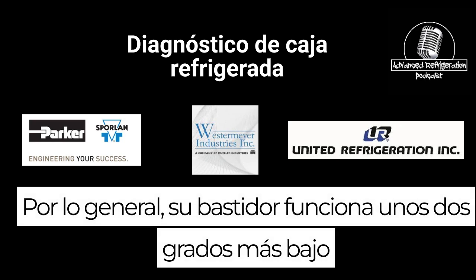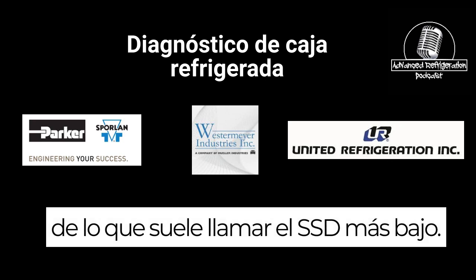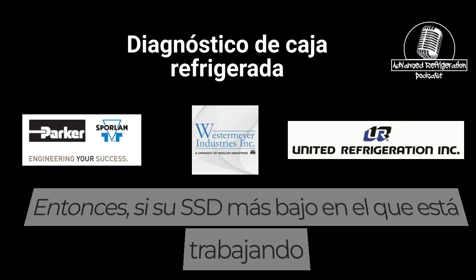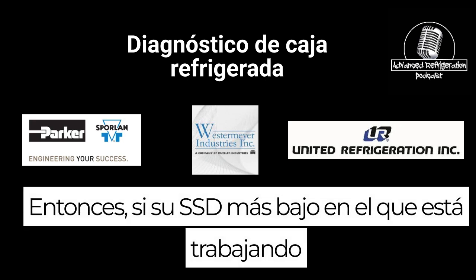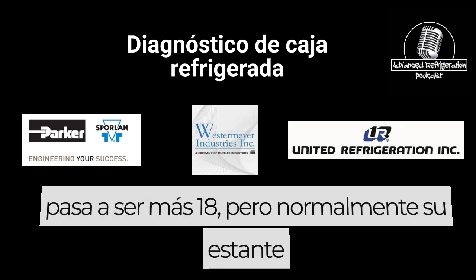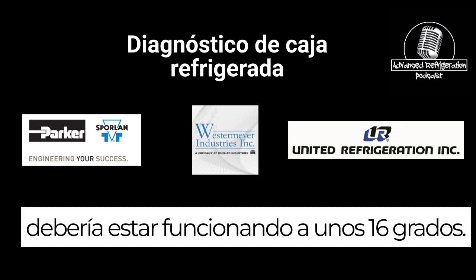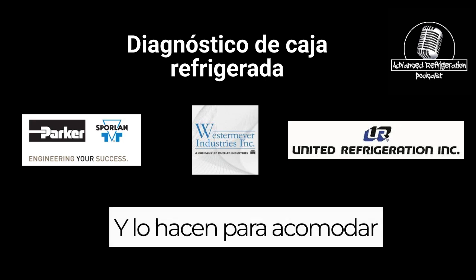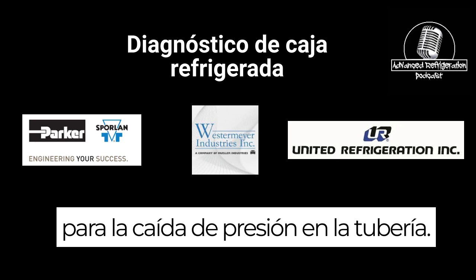Typically your rack is running about 2 degrees lower than what the lowest SST is typically calling. So if your lowest SST, which you're working on, happens to be plus 18, typically your rack should be running at around 16 degrees. And they do that to accommodate for pressure drop in the pipe.